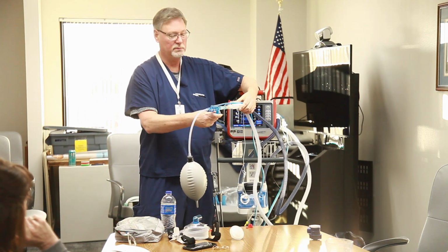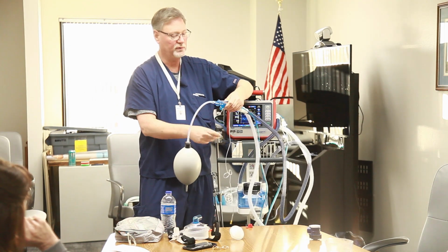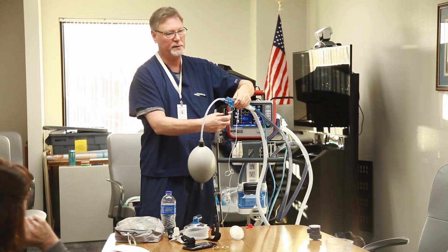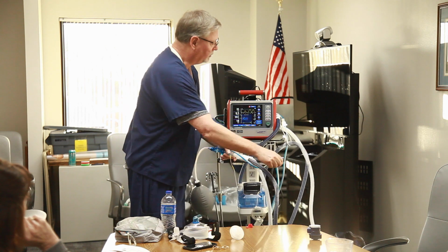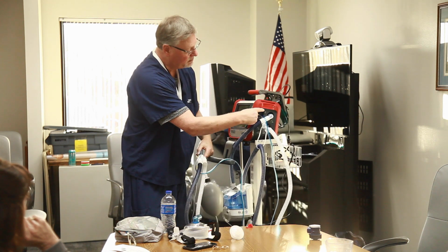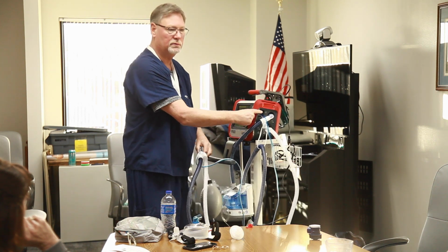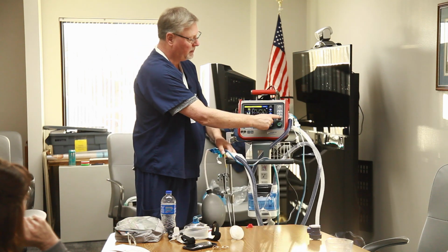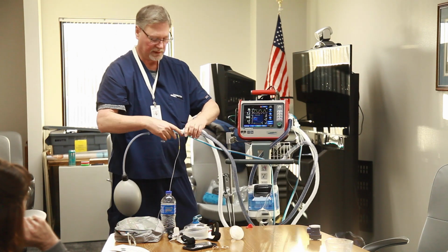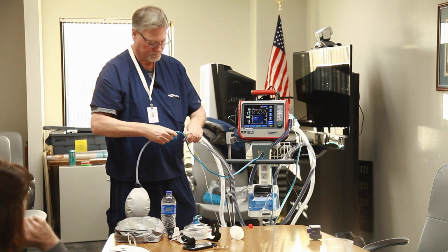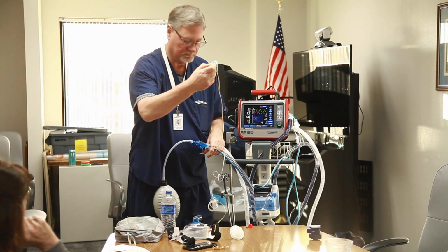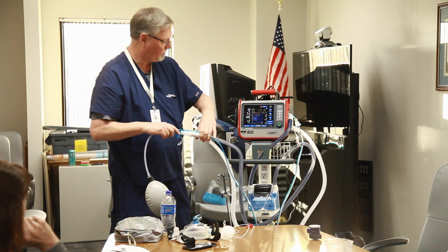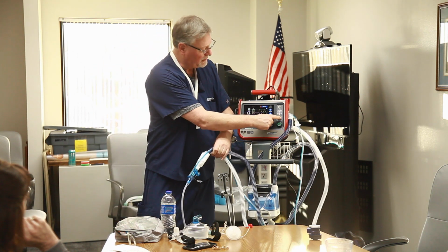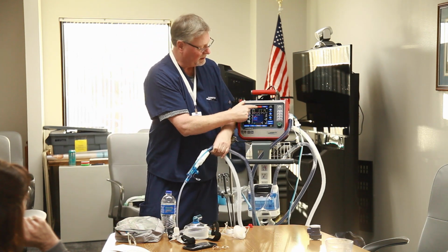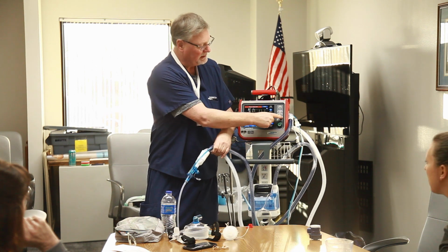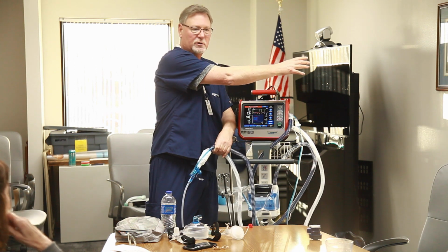The neb goes in here, just like you have T's already. It's spring loaded, so put your neb cup in here. Your O2 tubing will go right around to your nipple here, and push your little spray bottle here. You're going to notice I get an alarm for oxygen failure. I need to be hooked up to high pressure oxygen in the wall for it to work.